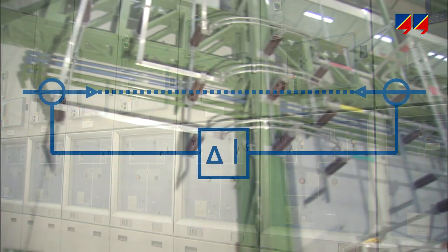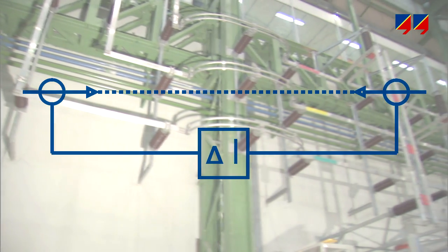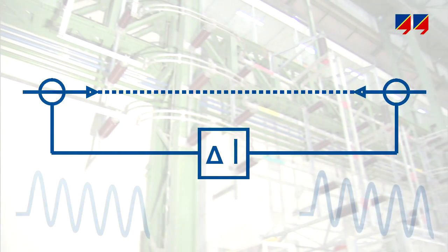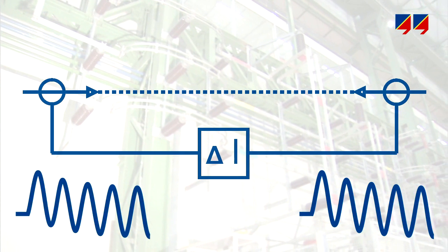And vice versa. Busbar, generator, or transformer differential relays may trip erroneously if saturation of individual CTs in the scheme causes current imbalance.